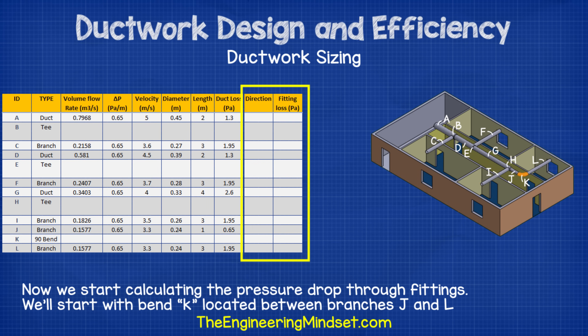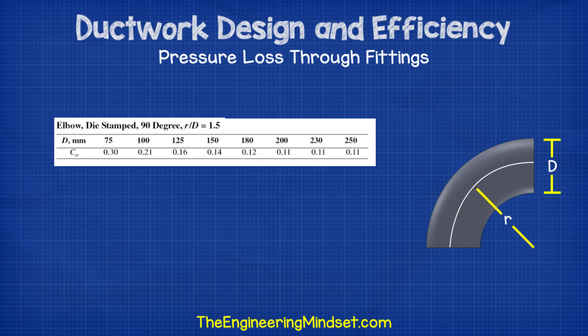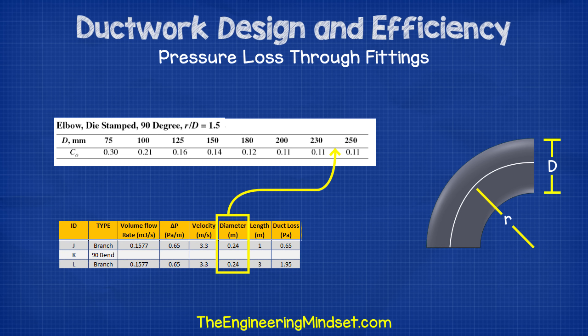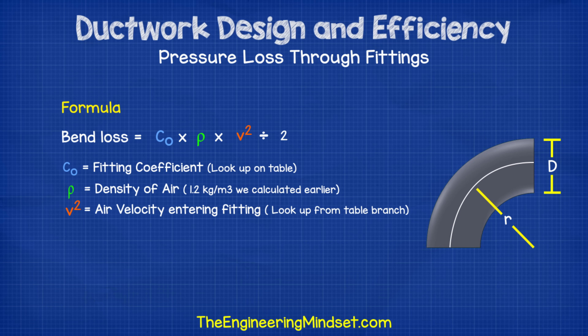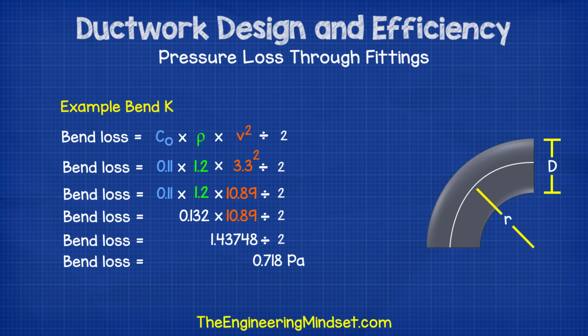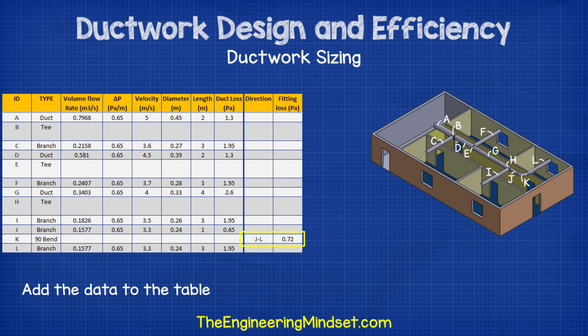Now we can start on the fittings. The first fitting we'll look at is the 90 degree bend between ducts J and L. For this, we look up the loss coefficient for the bend from the manufacturer or from the industry body. In this example, the coefficient comes out at 0.11. We then need to calculate the dynamic loss caused by the bend changing the direction of flow. For that, we use the formula CO multiplied by rho multiplied by V squared divided by 2, where CO is our coefficient, rho is the density of the air, and V is the velocity. If we drop these figures in, we get an answer of 0.718 pascals.